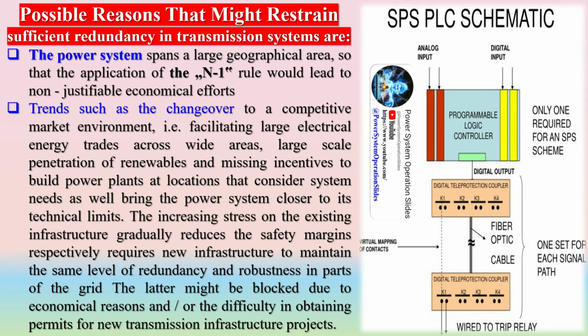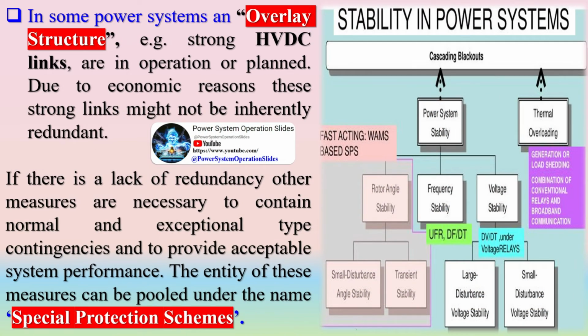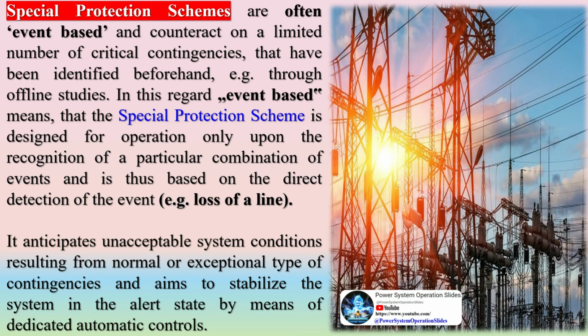On the other hand, it is not economical to design a power system arbitrarily redundant. In fact, it is necessary to find a technical and economical trade-off between investment cost, operation cost, and power system security needs. Possible reasons that might restrain sufficient redundancy in transmission systems are: the power system spans a large geographical area, so that the application of the N-1 rule would lead to non-justifiable economical efforts. Trends such as the changeover to a competitive market environment, i.e. facilitating large electrical energy trades across wide areas, large-scale penetration of renewables and missing incentives to build power plants at locations that consider system needs as well, bring the power system closer to its technical limits. The increasing stress on the existing infrastructure gradually reduces the safety margins, respectively requires new infrastructure to maintain the same level of redundancy and robustness in parts of the grid. The latter might be blocked due to economical reasons and/or the difficulty in obtaining permits for new transmission infrastructure projects.